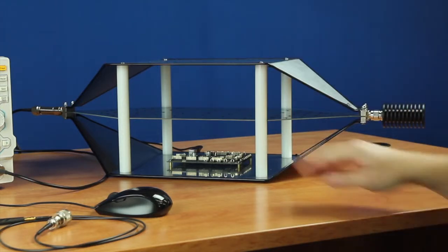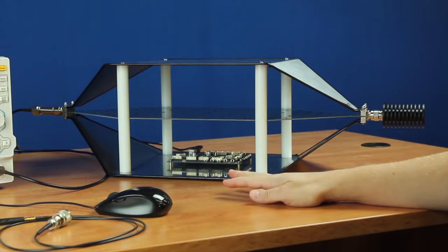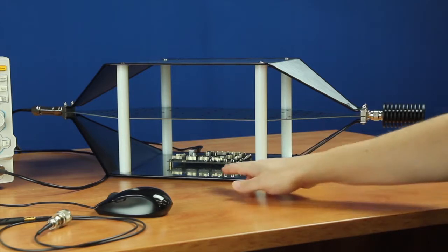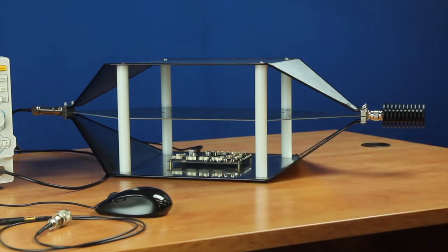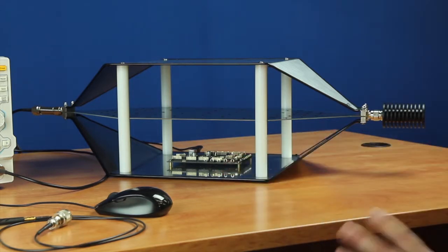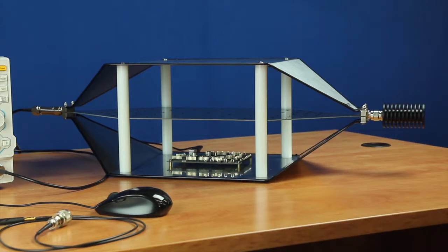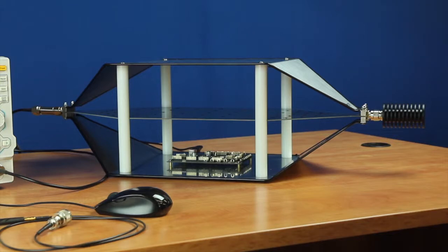In this setup, we put the device under test in the center of the cell, just above the bottom wall. It's estimated, as a rule of thumb, that spurious events with amplitudes higher than about 40 dB microvolts are problem areas in a TEM cell like this.